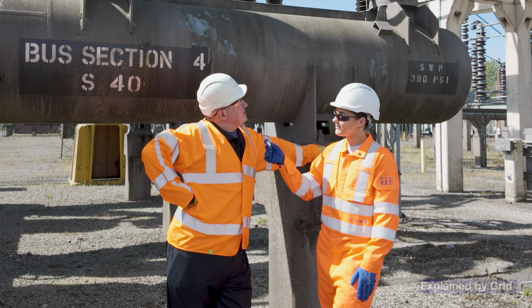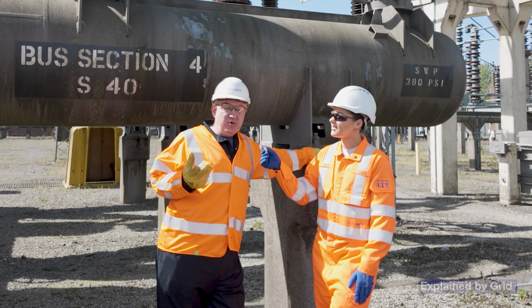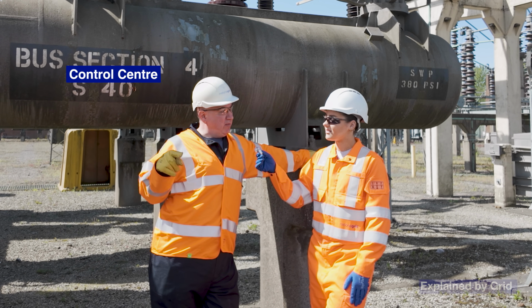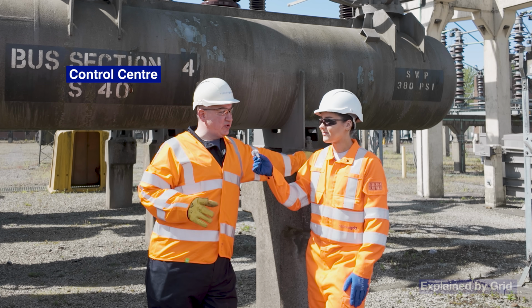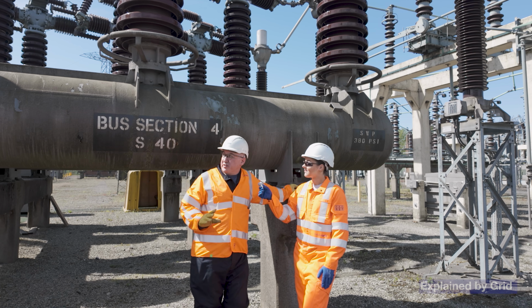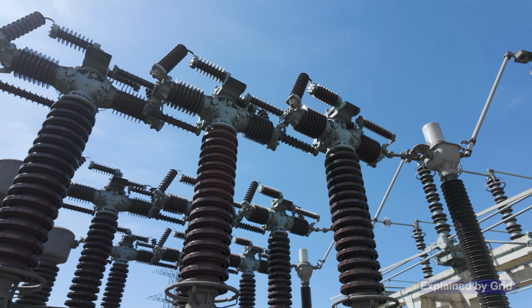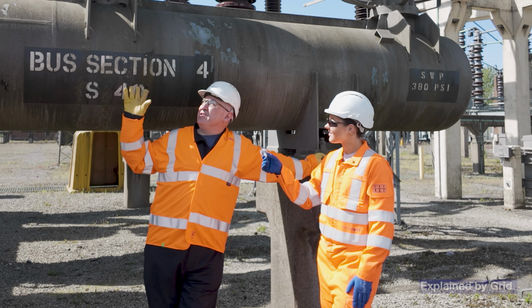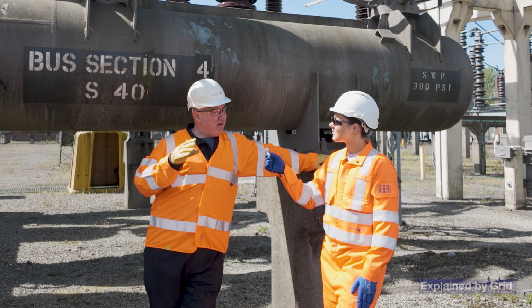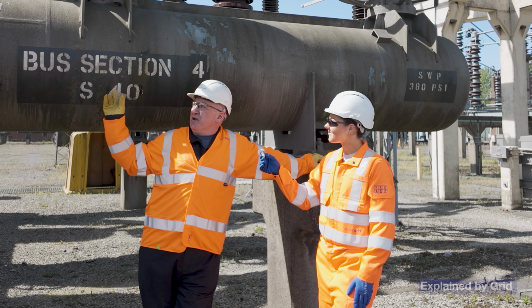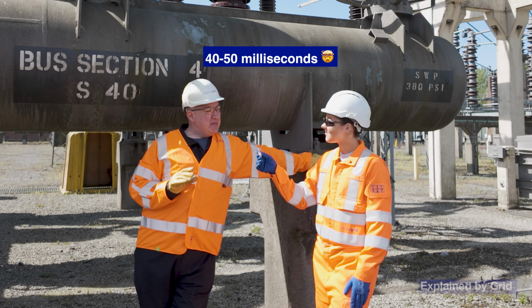Well, the first function we're going to talk about is switching, and there are 2 elements to it. There's switching from our control centre, but then there's also automatic switching. So we're standing in front of an air blast circuit breaker, and circuit breakers operate very, very quickly—this one in about 40 to 50 milliseconds.